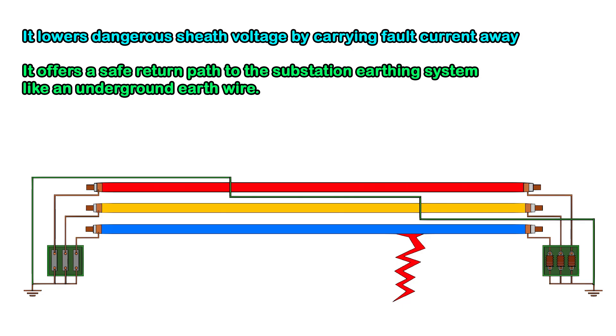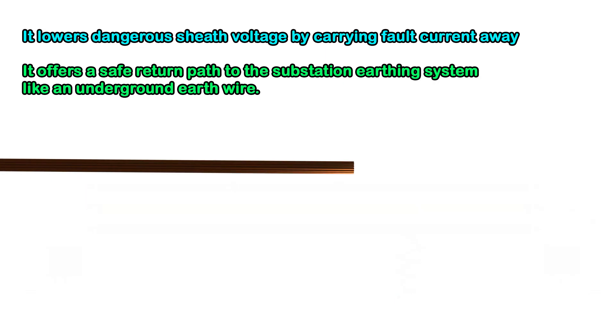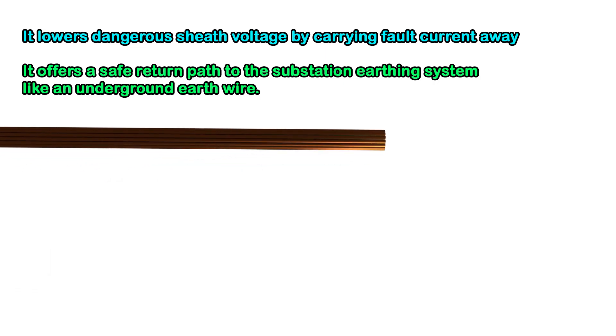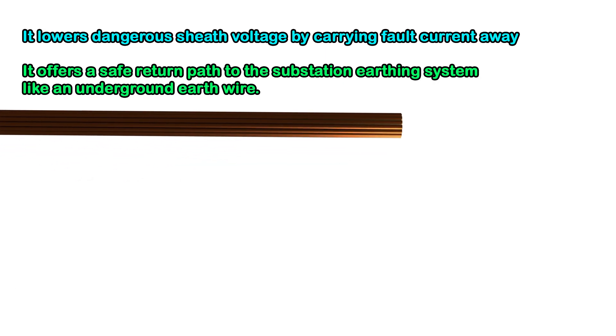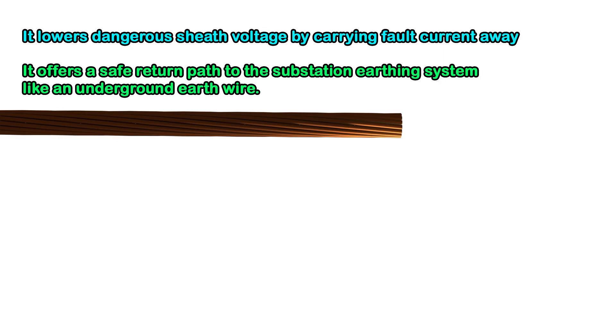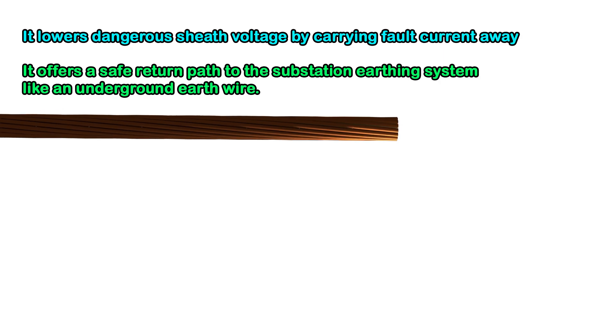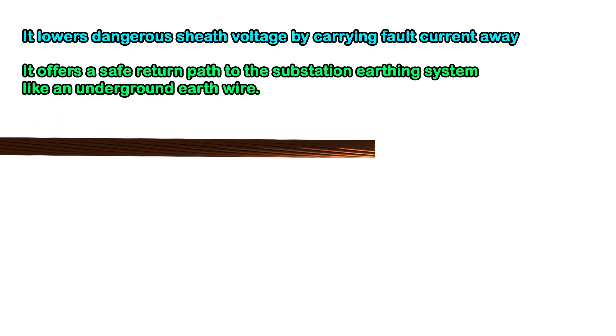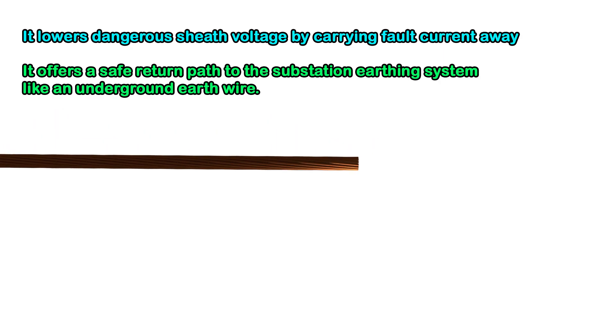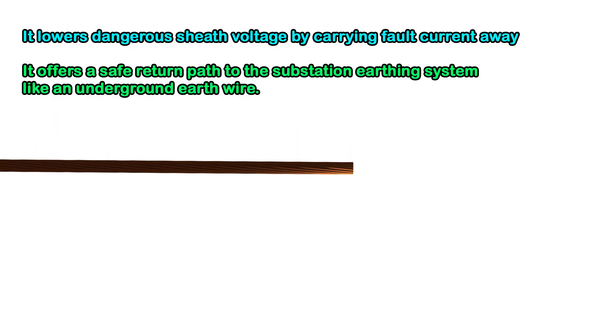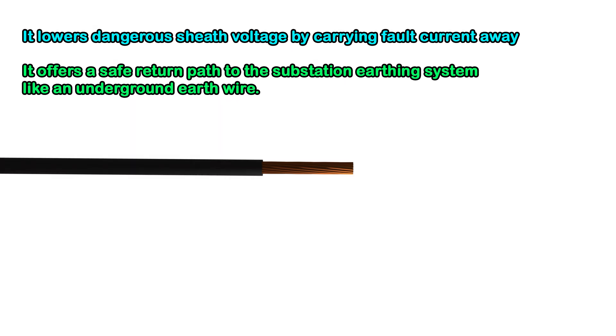ECC is finely stranded and twisted. This design increases the effective cross-section, reduces skin and proximity effects, and gives the ECC flexibility. We also insulate the ECC to provide environmental and electrical protection.